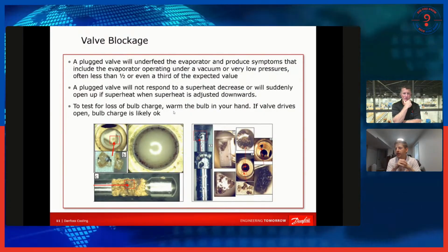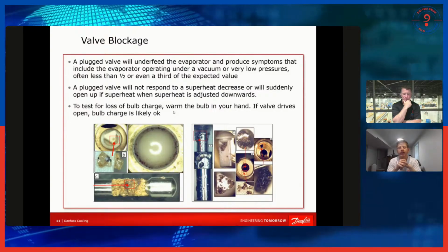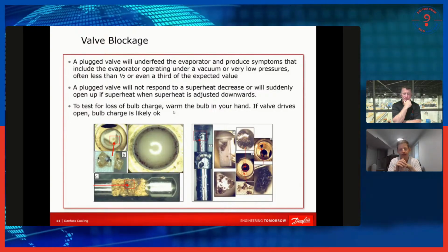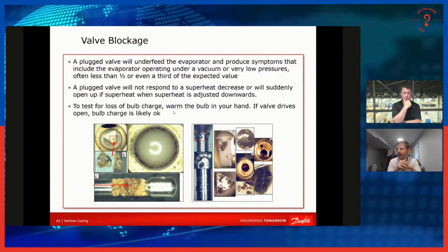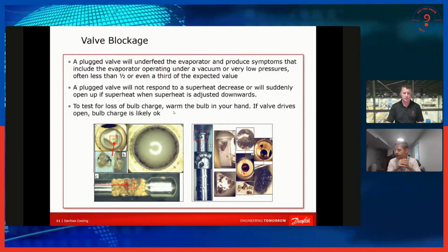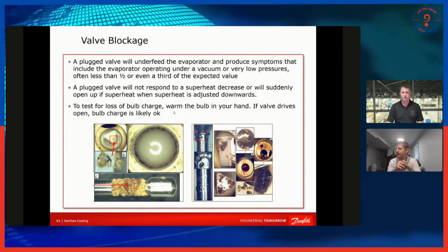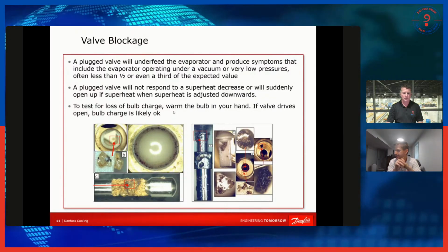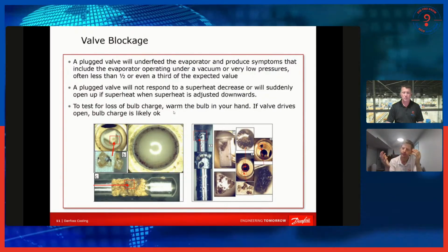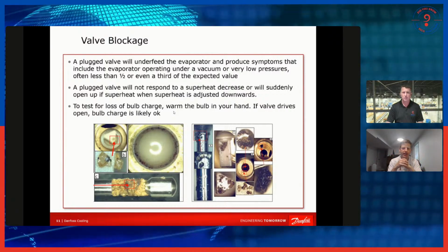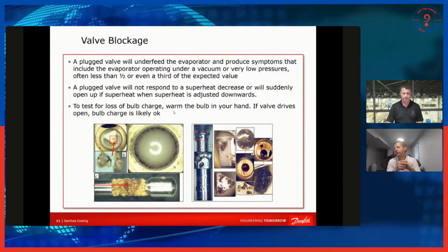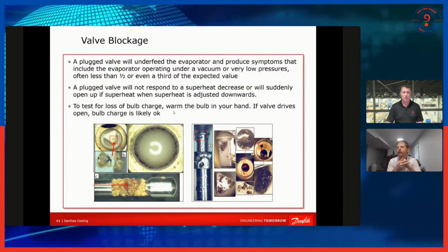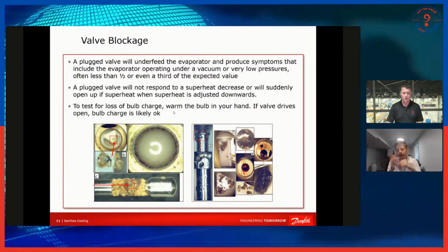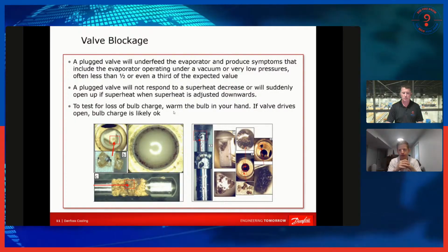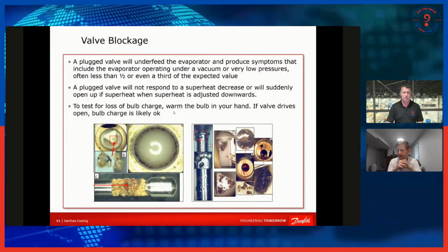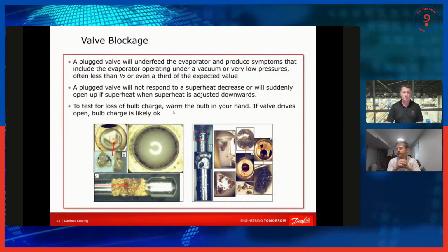Valve blockage. It's kind of a simple thing, but contaminants inside a system can plug up a TXV and they can plug up an EXV, and it's going to have a pretty similar effect on both. So I've got here some examples of pictures of different valves Danfoss has taken apart that have contaminants. I think all of these are TXV examples, but it looks the same inside an EXV, whether it's scale from not flowing nitrogen, burnt oil, or some sort of other sludge that comes from chemical reactions from having random outside contaminants. It can definitely gunk up and restrict flow through an EXV.